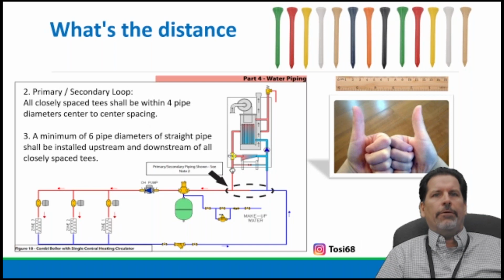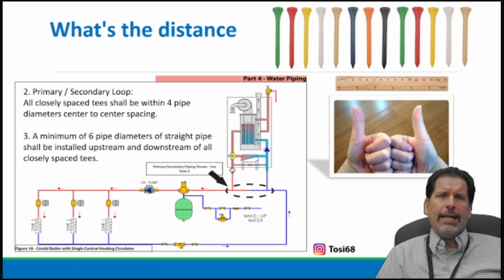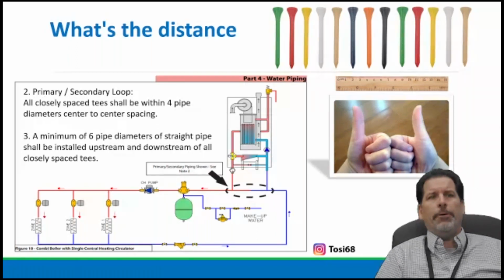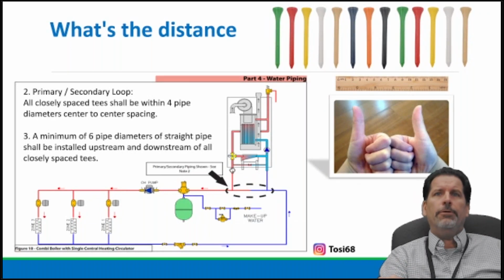Now, everyone always focuses on centers, but the pipe coming into your first tee needs to have 6 pipe diameters of straight pipe before and also leaving. That, again, is part of what we do with decoupling our boiler from our heating system.